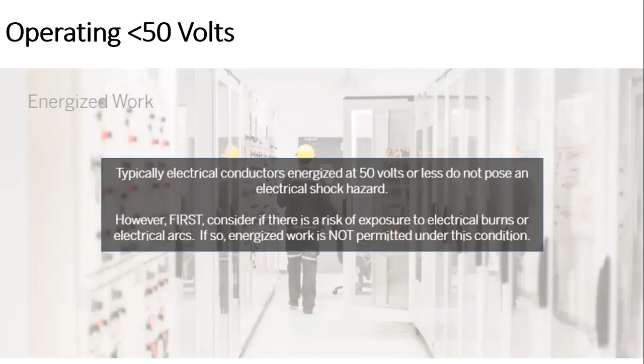The incident energy is measured in cal per centimeter square, and it is from 0 to 40 cal per centimeter square or even higher. The personal protective equipment for arc flash is available up to 40 cal per centimeter square. If the incident energy is more than that, you have to work in shutdown format. You have to create an electrically safe work condition. Energized work is not allowed. We are going to discuss this in detail because these are very in-depth topics. In order to do live work, for the voltage level, if you're working at less than 50 volts, you are permitted to work. But if you are working at greater than 50 volts as per NFPA 70E, you have to create an electrically safe work condition.